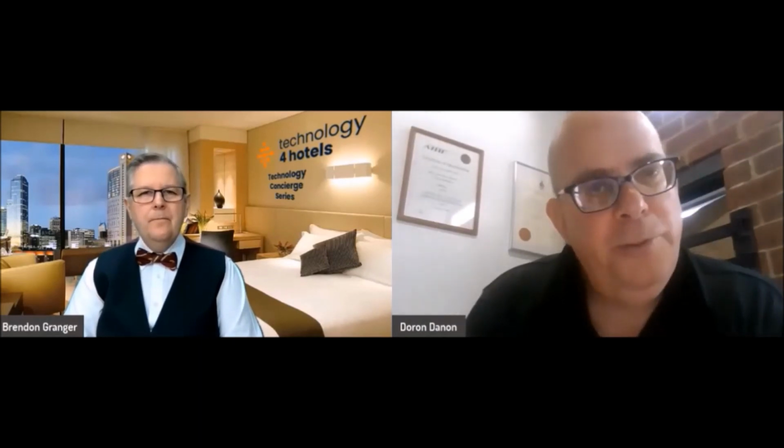And if it doesn't detect any motion within that predetermined timer period, then the system would be confident to know that the rooms are vacant, and only then would it take control and do whatever needs to be done when the rooms are vacant. And as I explained, it could either be set to be switched off completely, or to be doing a temperature setback on the HVAC side, depending how the hotel wants it set up and what they're looking for in the form of energy savings.